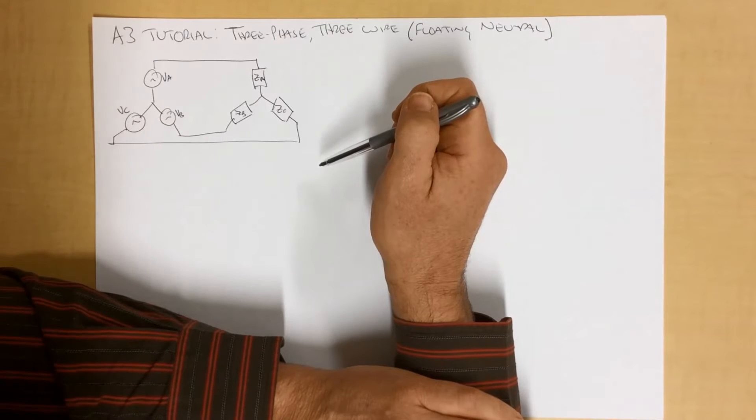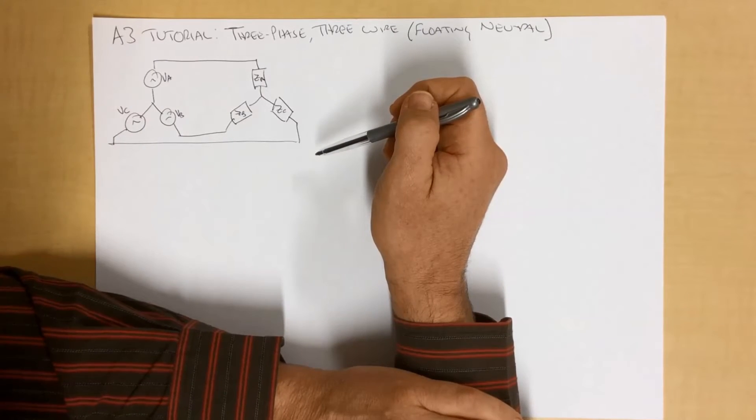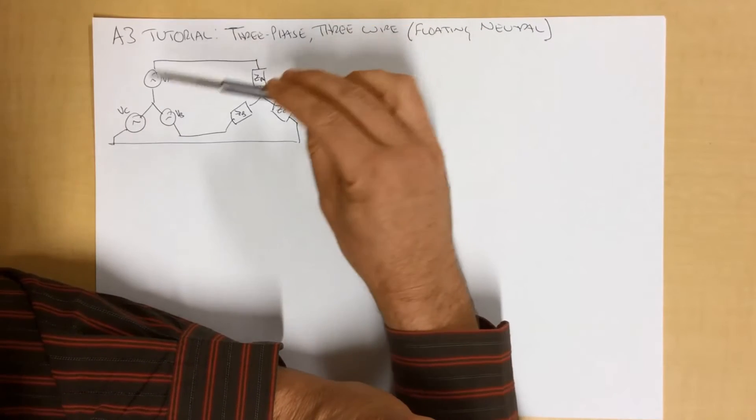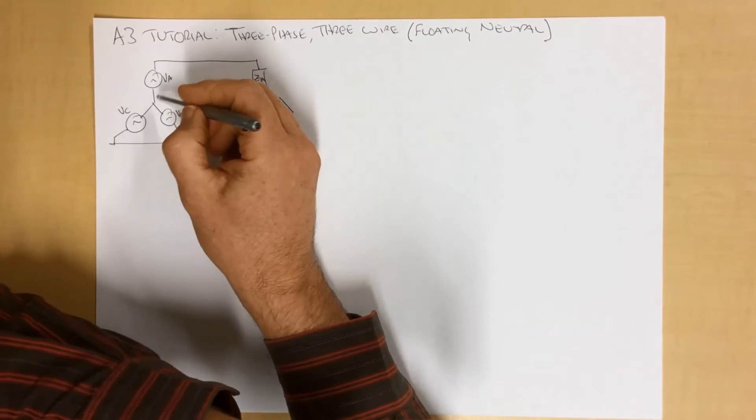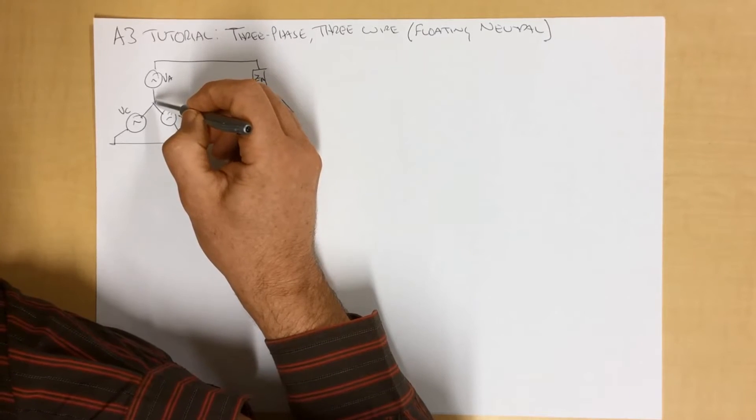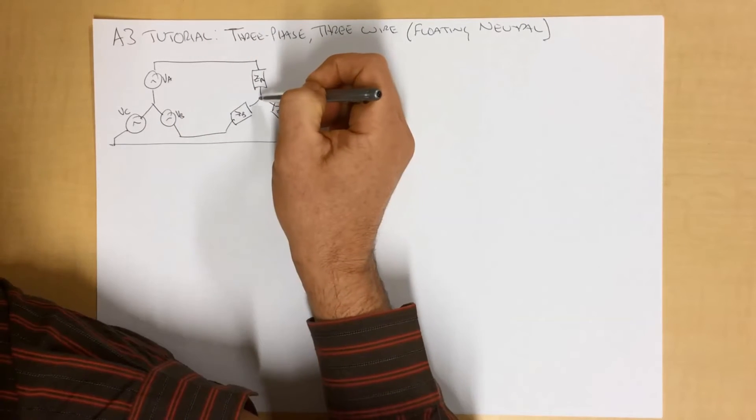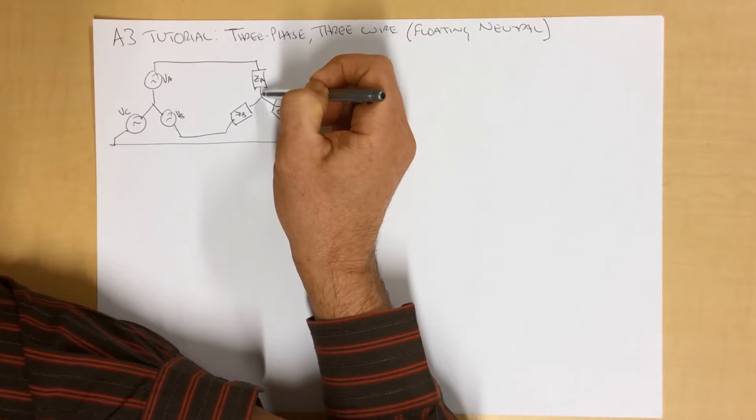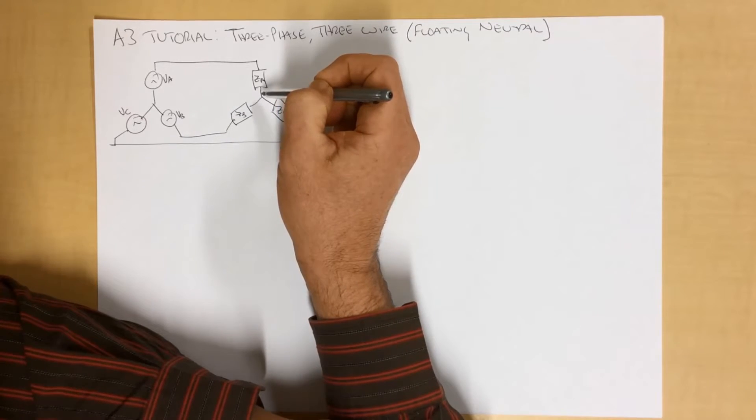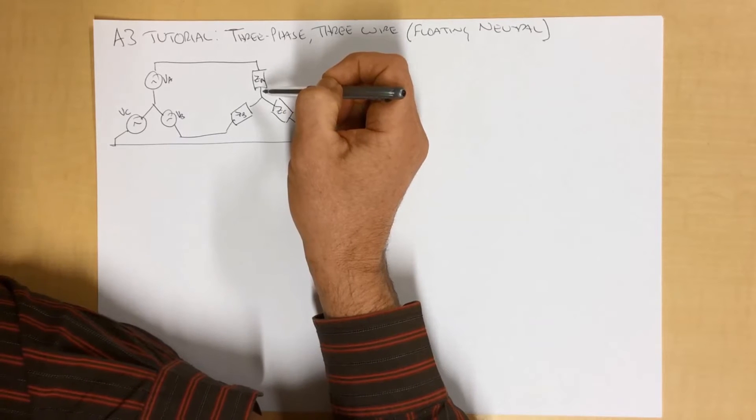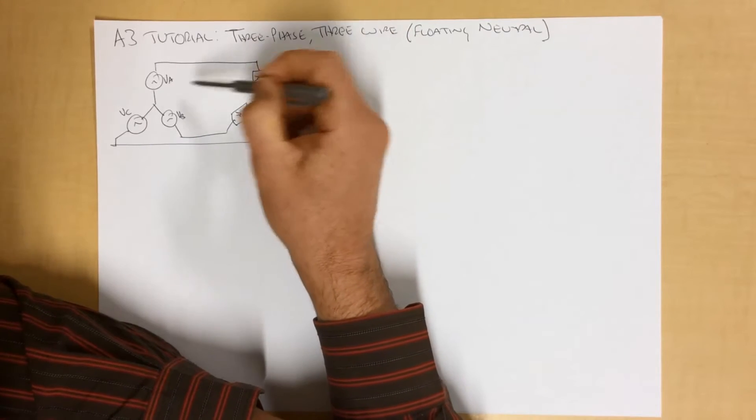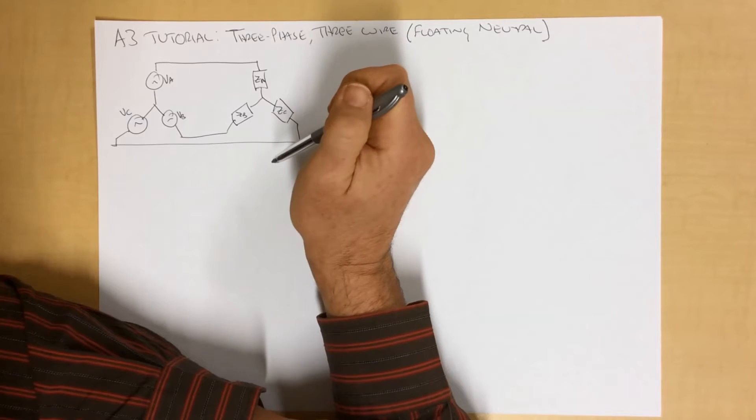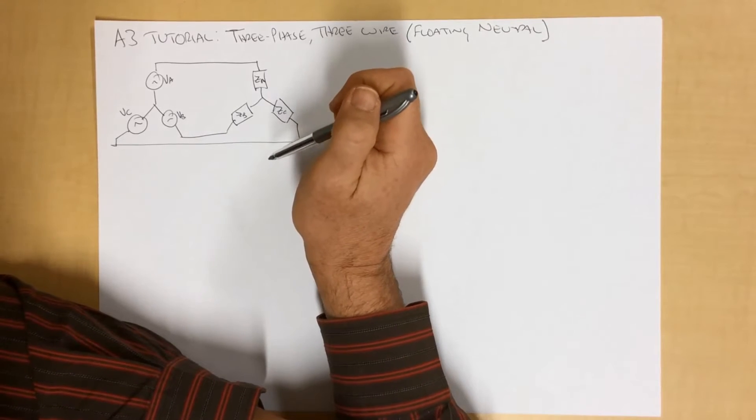Now a commonly misunderstood or misassumed thing is that the neutral point here, which is often tied to ground if it's a transformer or something like that, this point here, a lot of people assume is the same voltage as this point here. That is not always the case. In fact, it usually is not the case unless this is an idealized system. If it's a perfectly ideal system and everything's perfectly balanced, then yeah, sure, they will be the same. But that's more through coincidence than actual reality.